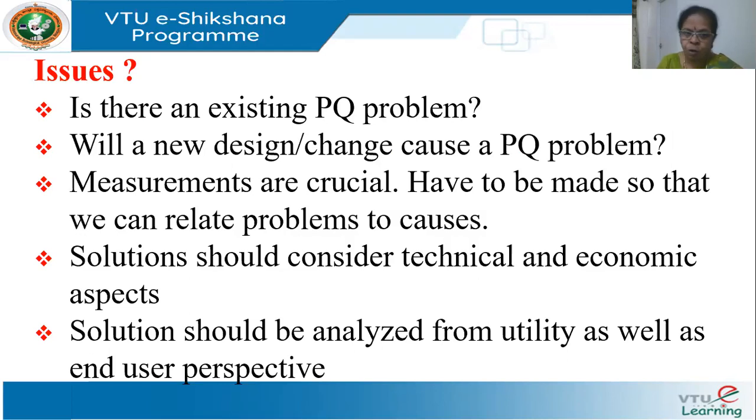Okay, I put an inverter, fine. Your inverter solves the problem of the voltage sag. So I can compensate and keep the voltage magnitude to its original value, but this inverter is going to introduce harmonics. So I have solved the problem of sag, but I'm introducing harmonics. So what happens? I have to put filters.